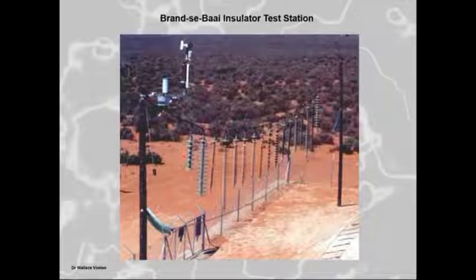Well, what came from these results is that we connect these up with fuses, and these fuses are normally 750 milliamp where they blow. Not a single fuse went, and then further on the current levels, we were measuring in the tens of milliamps. We didn't reach 100 milliamps on any of them, so the tens of milliamps we reached. So it's not the pollution measurements is light and medium. The currents we're measuring on the insulators at the closest area to the problem is in the tens of milliamps. And so it's not the leakage current is not showing it, and the pollution measurements is not showing.